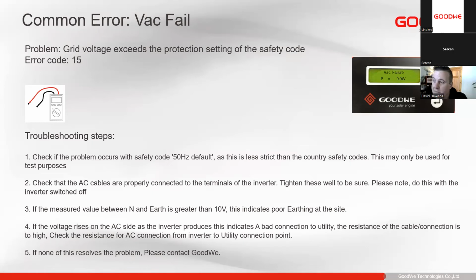So what we can very often do, we can set the inverter to, let's say, 50 Hertz grid default. That will then not comply to any grid codes whatsoever, but it will give you a wider range of input. If it then operates, then we can be quite certain that it is some grid code related safety error. We can then verify the voltages of the utility, make sure the AC cables are properly connected, and restart the inverter.